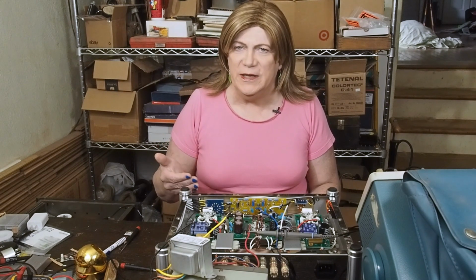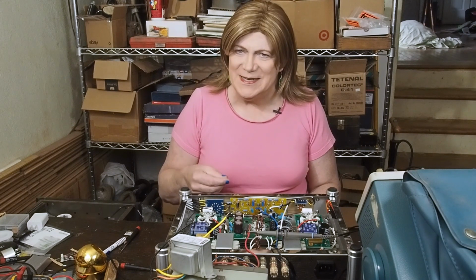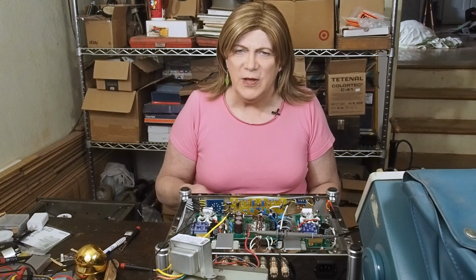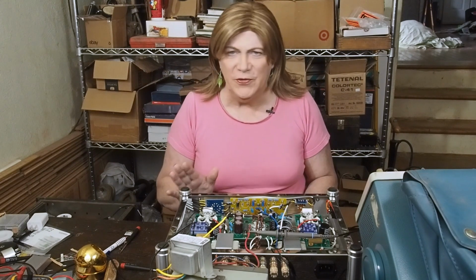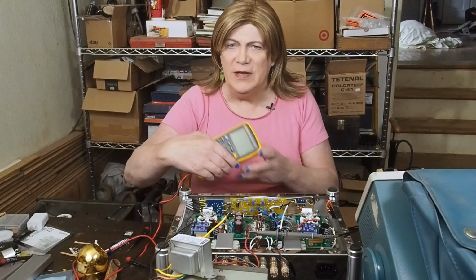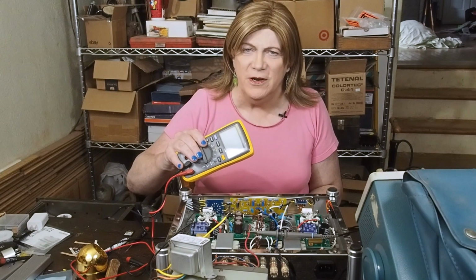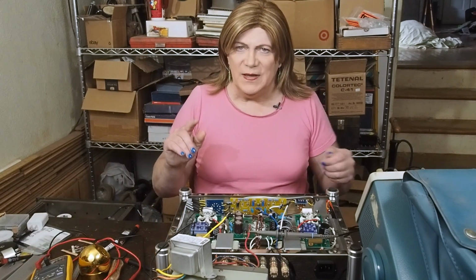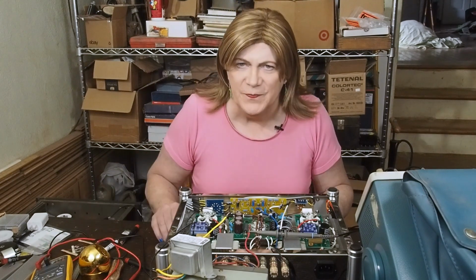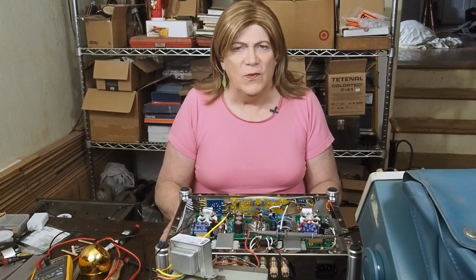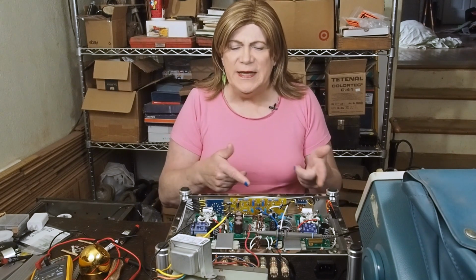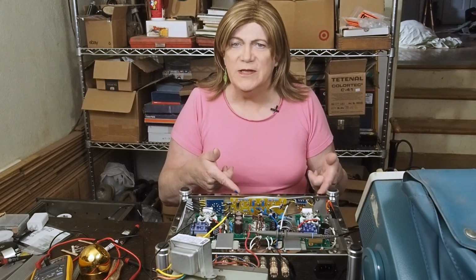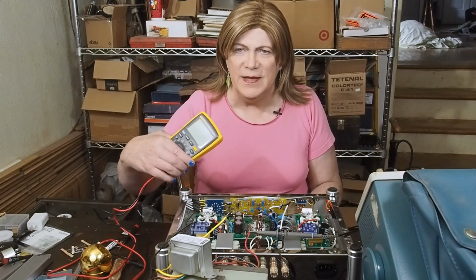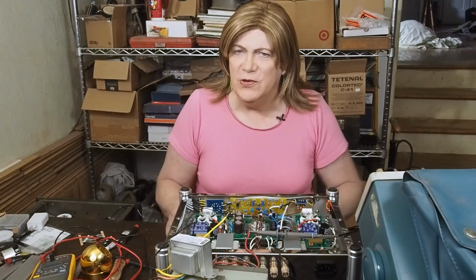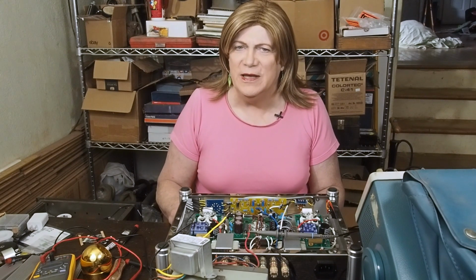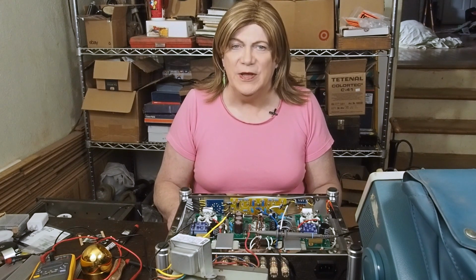The confusing part is that resistance and impedance are both measured in ohms, but they are two different things. We have our little meter here that we all know and love that measures in ohms, and we can measure DC resistance, or DCR, with this meter. You'd think, well, why can't I just measure the leads or across the terminals of my transformer with my trusty little meter and get the resistance? Well, you can, but that's the DCR of the transformer, which has nothing to do with the impedance.